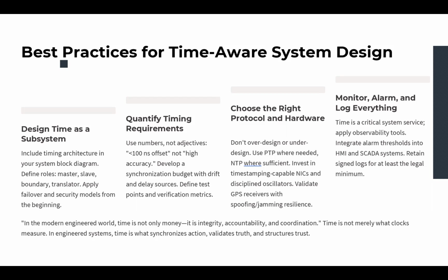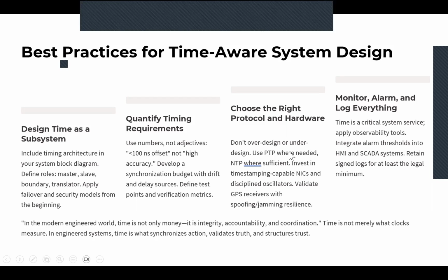Alarms should not only be generated for synchronization losses, but also for slowly degrading behavior. If we have rising jitter, we should have an alarm. If we have slow servo convergence, we have to have an alarm. If we have a backup source drift, we have to have an alarm. All of them should be recorded. This is how we make sure that we are following best practice for time-aware system design.